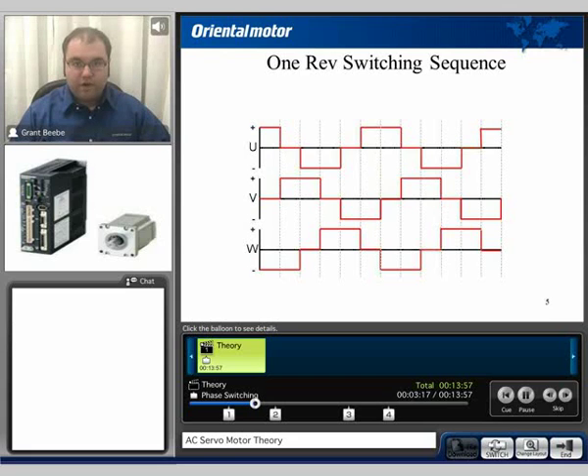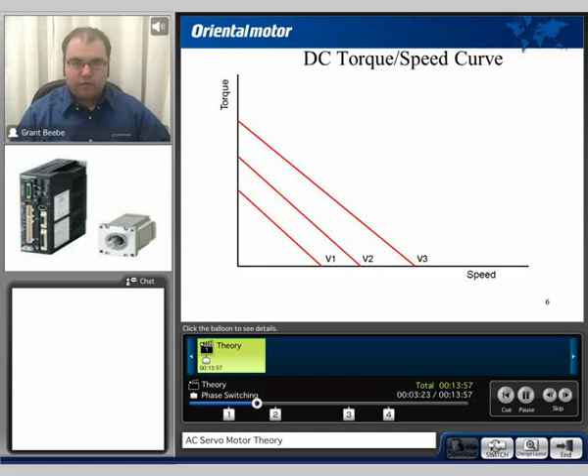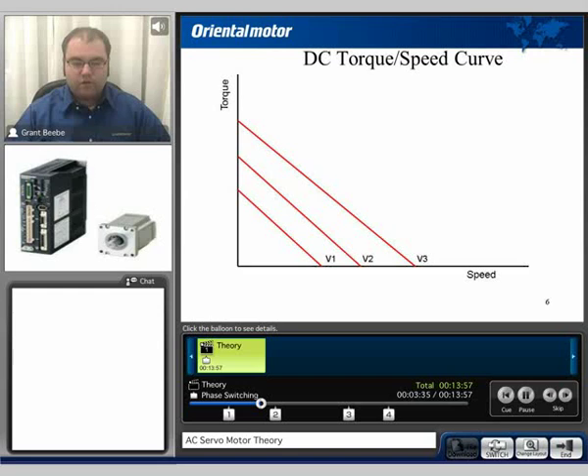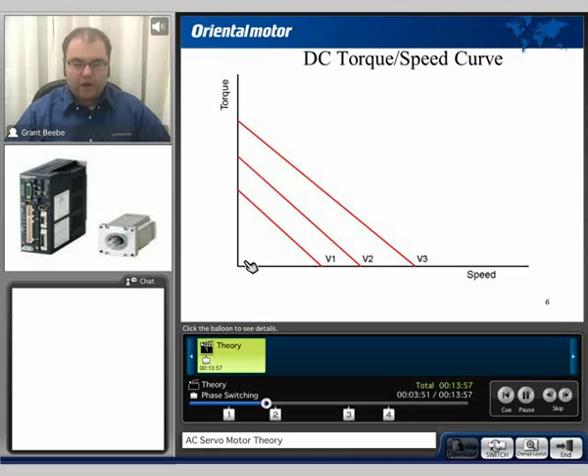By changing the frequency of how fast these switch on and off, we can change the speed, and ultimately we can control the amount of rotations by keeping track of the switching as well. An AC servomotor is going to have what is typical of a DC torque-speed curve. Because it is a permanent magnet motor, as the voltage increases to the motor we can increase the output torque and ultimately the speed. On this chart with torque on the vertical y-axis and speed on the horizontal x-axis, different voltages — voltage one, two, and three — show different performance based upon the level of voltage.